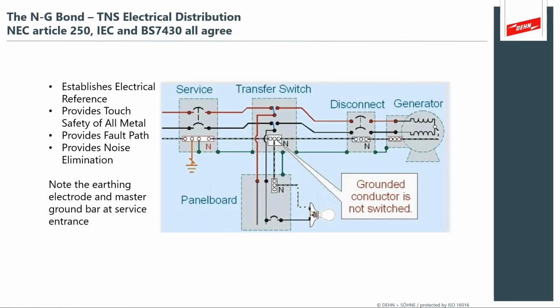So I mentioned it already, at your service entrance, you'll have what's called your neutral ground bar. And this is what you see in Article 250, what you see in the IEC standards, the British Standard 7430, they all agree. You have to have a single point of bonding for your neutral and your ground. And this establishes your electrical reference. It provides touch safety of all the metal. It provides a fault path. And this is how you eliminate noise and interference in your electrical systems.